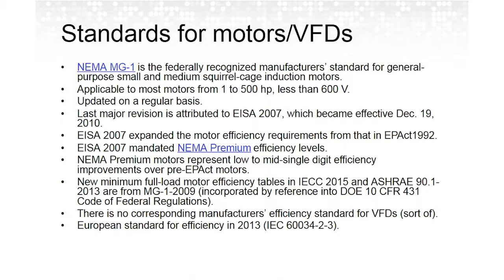Basically, the change associated with the Energy Independence and Security Act of 2007 was that what was originally considered a NEMA premium efficiency motor became the de facto standard as far as minimum efficiency requirements. And again, this is mandated on a federal level for all manufacturers.